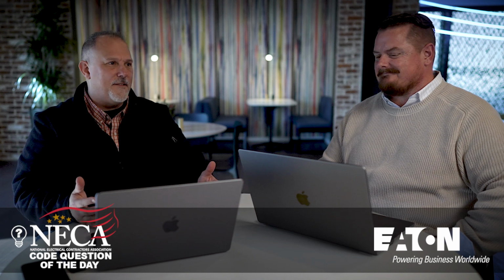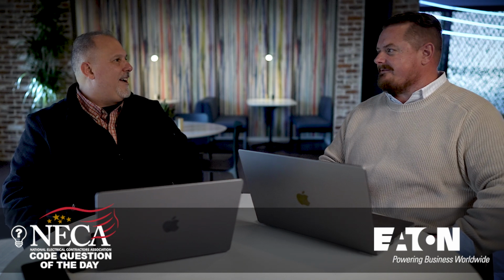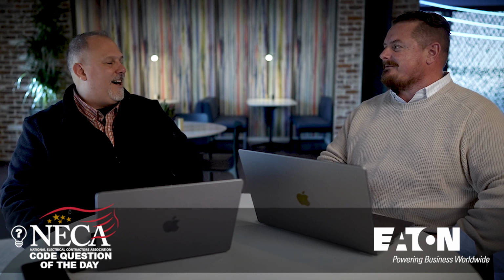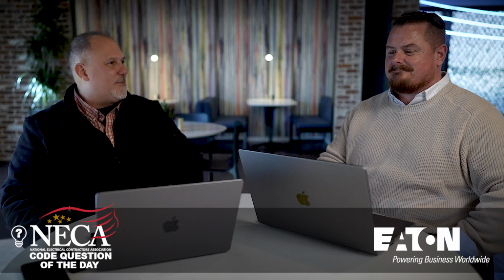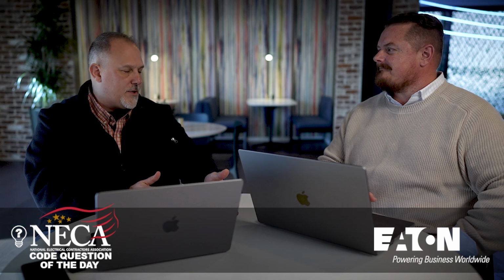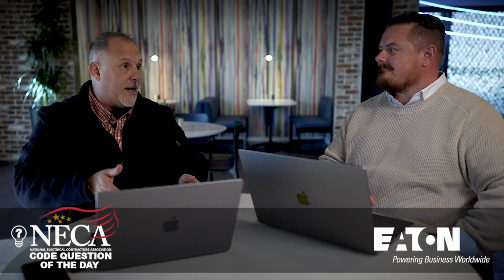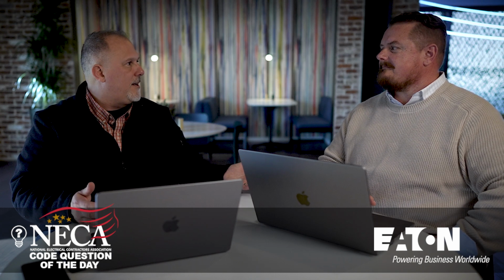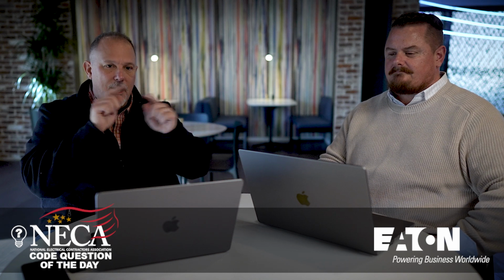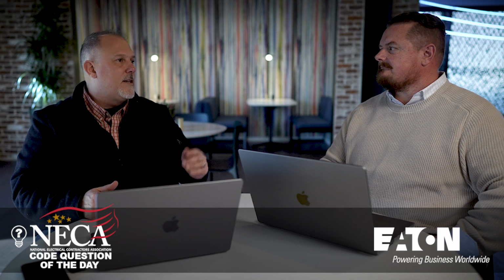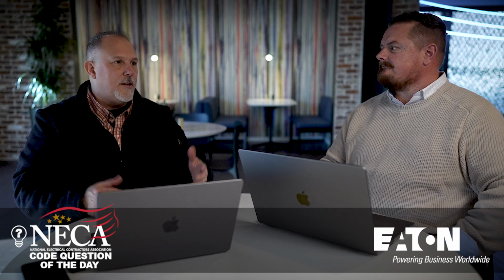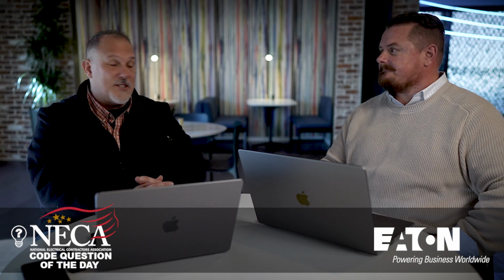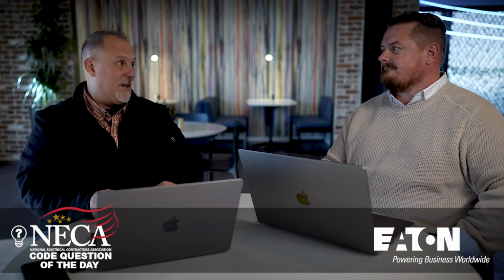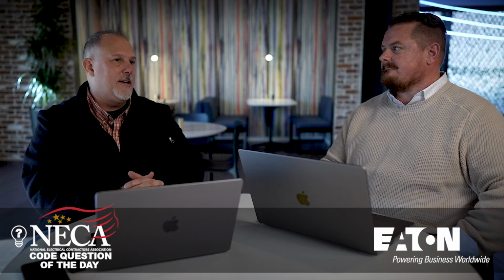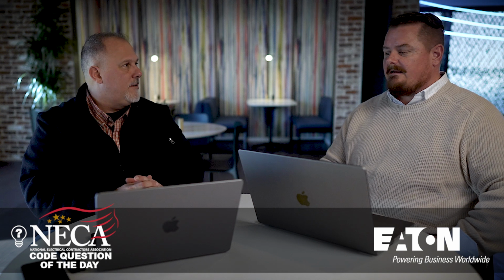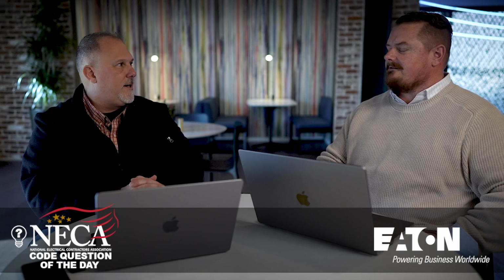So then I looked it up and sure enough, everything, conductors, devices, anything that is going to have current going through it is going to have a short circuit current rating. I was absolutely amazed. It was 2,000 amps out of the box, and then you could buy a 10,000 amp device with a short circuit current rating. I started looking at different manufacturers and all the literature, and sure enough, you can buy a 10K. They're all 10K, but you buy the wrong one and you're going to have to replace it. So I had to buy one, and then I bought an extra one for the desk because it was a teaching moment. The moment I learned something, I like to share it, because if you don't know, think of how many other people don't. Well, that's exactly right.